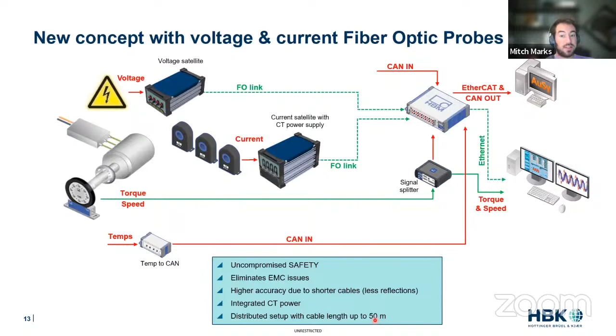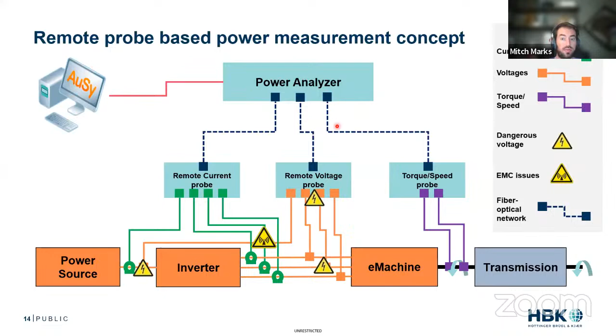So what does that look like in my little animated diagram? Well, we have our power analyzer with fiber optic links going to our probes. Eventually we will support torque and speed as well. Initially, it'll just be voltage and current. We automatically cut out long cable lengths. We reduce the number of cables so that we lower the amount of EMC. It's still there because the inverter is still there. But we significantly reduce that EMC risk and we completely decouple the instrument and the users from the high voltages. So it's extremely safe.